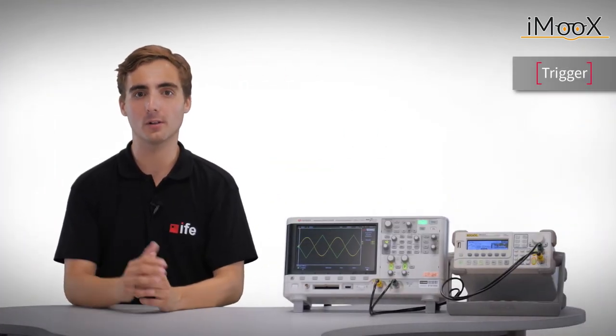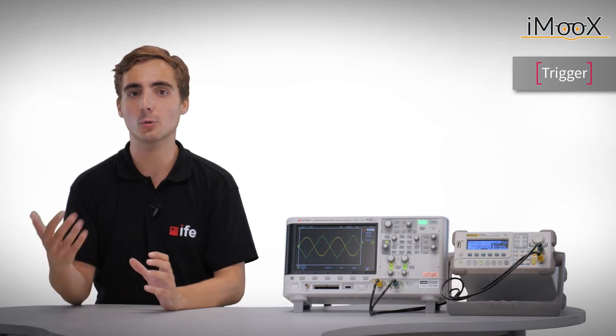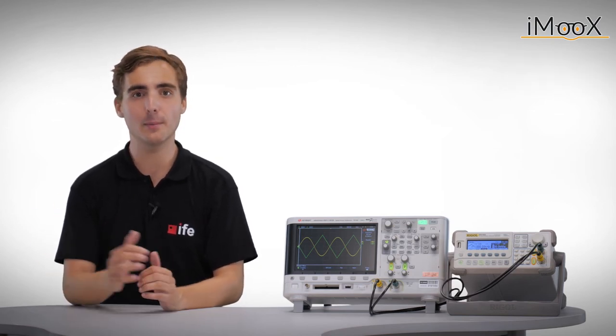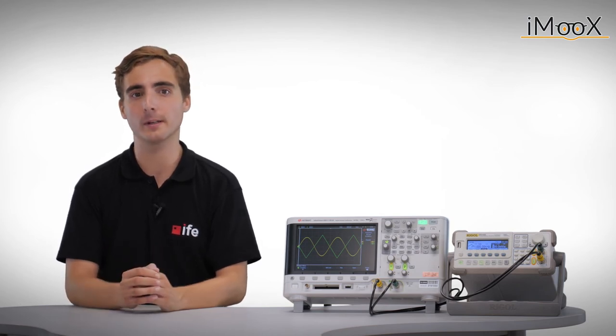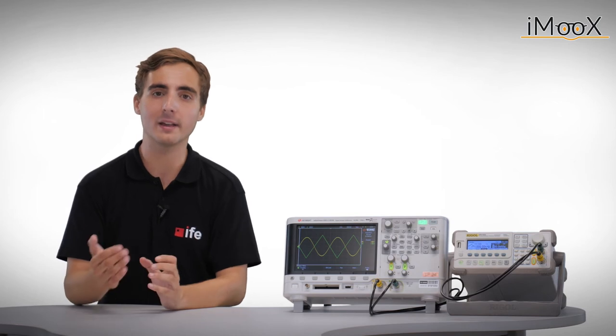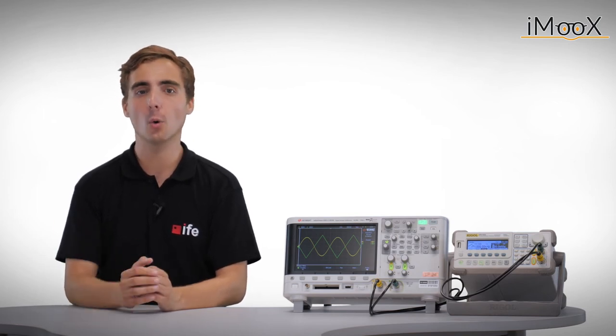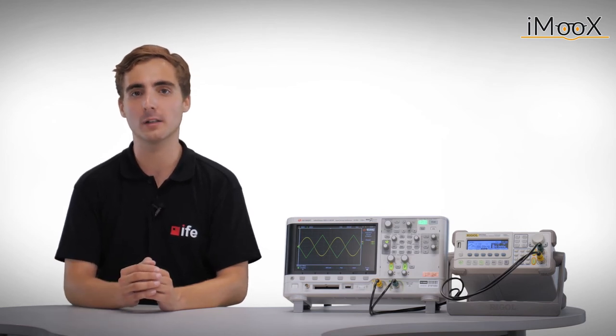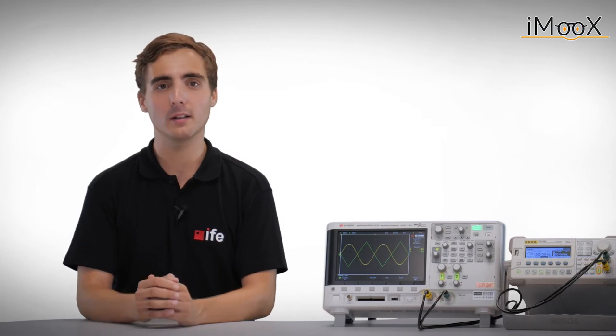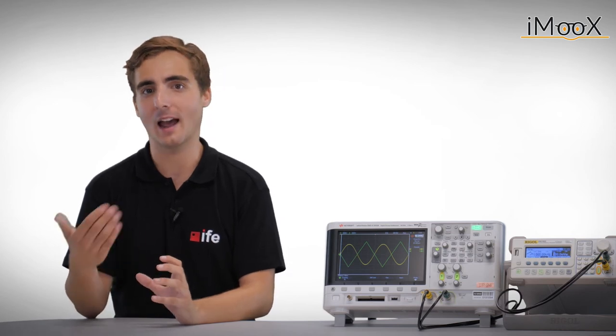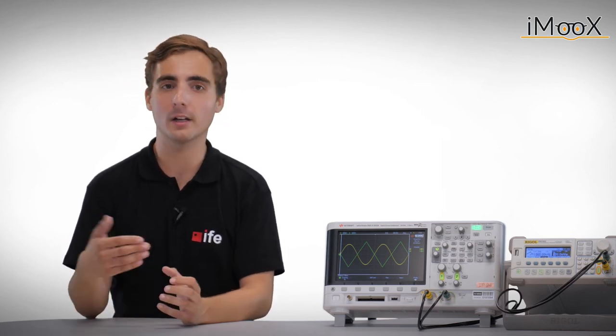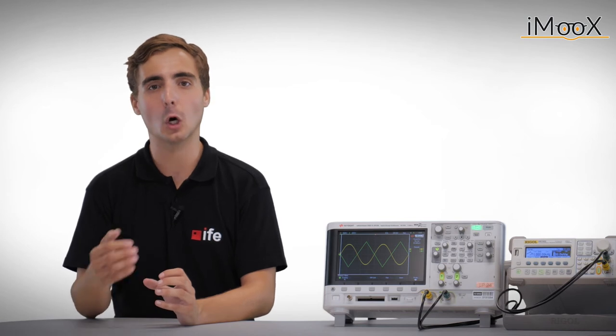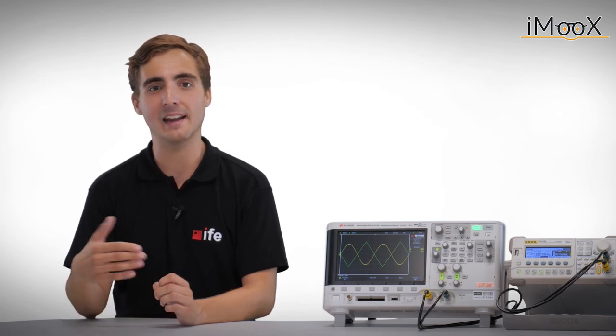Now, we come to a very important topic, which is the so-called trigger of the scope. In the previous examples, we always had a stationary image on the screen. But we have to ask ourselves, why is this the case? How does the scope know when to start a new recording? This can be done by setting appropriate triggers. The recording is triggered when a defined event occurs. In general, there are many different types of events that can be fired depending on the channel signal. In this tutorial, we will focus on the simplest and most commonly used one, it's the edge type trigger event.